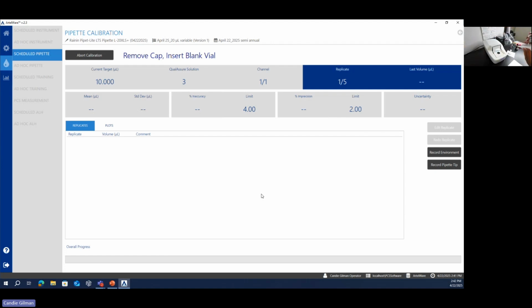So the system keeps track. You keep adding your red dye dispenses into that blank vial, and when the system tells you to change it, you change the vial. So the software, you can see it says remove cap, insert blank vial. So I'm going to go ahead and remove that cap, insert the blank vial. And now that I've inserted it, the software says, please close the lid. So this PCS instrument also has a capacitive touch sensor lid. And what that means is I can just touch the side and the lid will close and the vortexer will start vortexing.